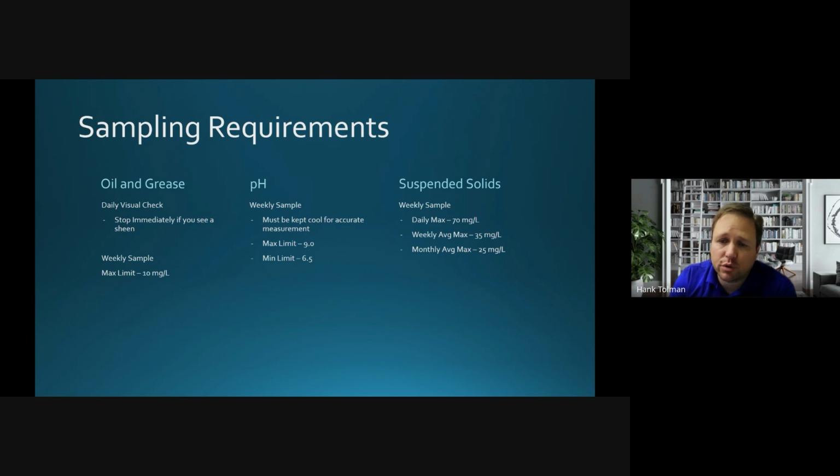We typically don't have more than 2 samplings going on at a time. If we need to, we can buy 2 more sampling kits so that basically each of the inspectors can have one as they're going out to do the dewatering sampling. As long as we take those testing kits out there, you collect the water in the regular bottle that you're going to collect it in, and then you pour it into one of the test tubes from the sampling kit and test what the number is, right? And then you take whatever number pops up and you divide it by 3, because that's testing for NTUs, and what Utah looks for is milligrams per liter, not NTUs.